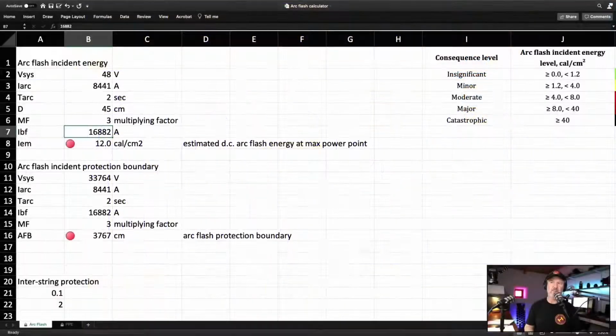But there is a solution to this, so I'm just going to jump back. The solution is we need to reduce the arcing time. This T-arc is the arcing time for this battery system when there is a bolted fault or short circuit. And the arcing time, in the standard, should be listed as 2 seconds if there is no string overcurrent protection. Now, as soon as you've got a multi-string system, you're required to have string overcurrent protection. But you can even put string overcurrent protection in there anyway, even when there's only one string, typically at a midpoint, to reduce the arc flash incident energy.